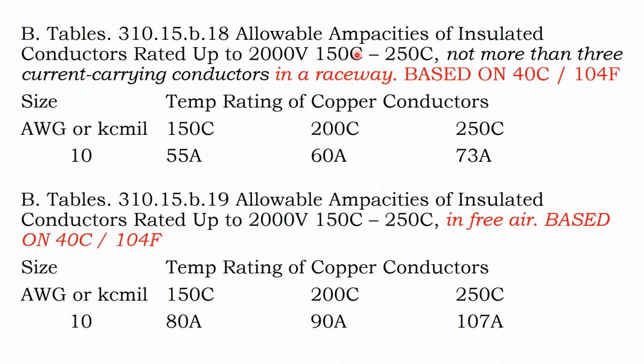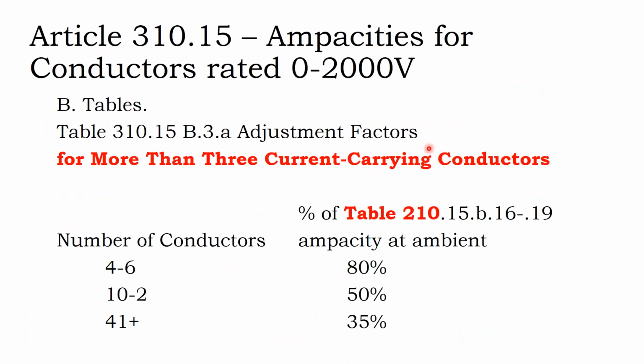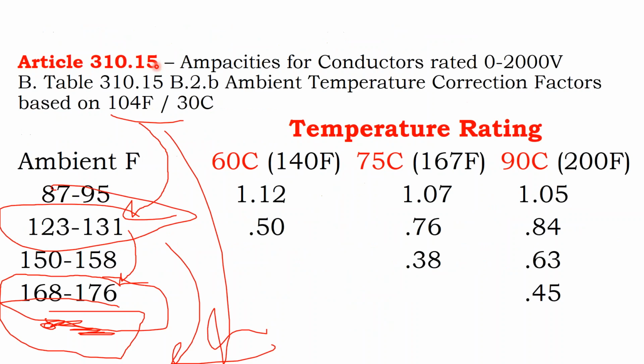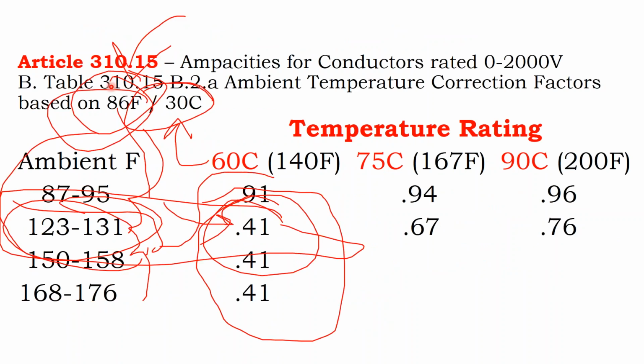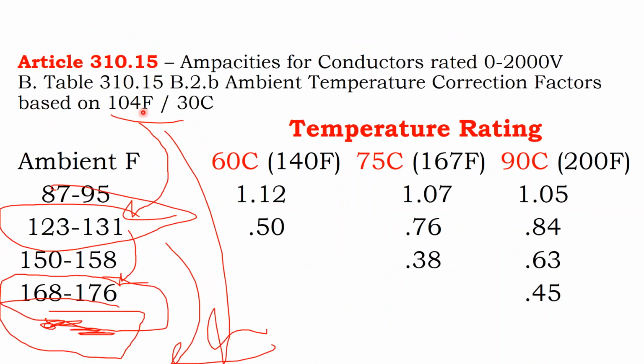And then we get into charts that are exactly the same as what we just saw, but instead of being done at 86 degrees Fahrenheit, they're done at 104 degrees Fahrenheit. Remember, with all these charts, you're not actually calculating anything. You're just matching up the values on the charts because you're not an electrical engineer in this circumstance.